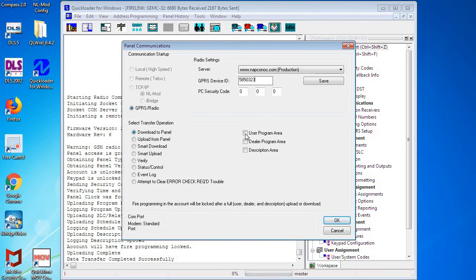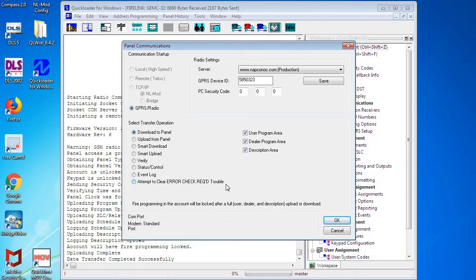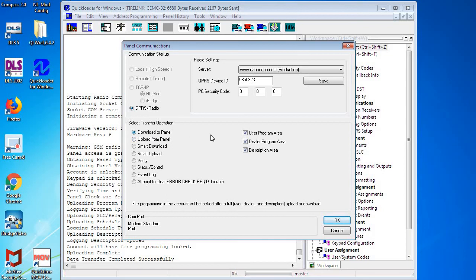Now before this is done, it's very important that the Firelink panel is unlocked and Enable Programming is selected, and the fire panel is in error check mode. You can always upload and take an event log or status without a technician on site, but for NFPA and UL regulations, you must have a technician on site after the download to test the system. So in order to send a fire change to this panel, the panel again must be put into error check mode, and that's explained in another video—we'll also post that link below.